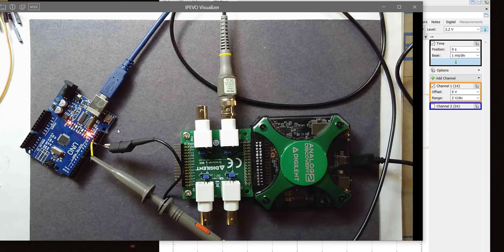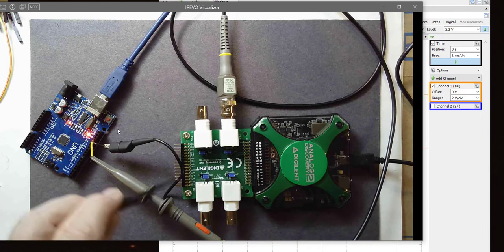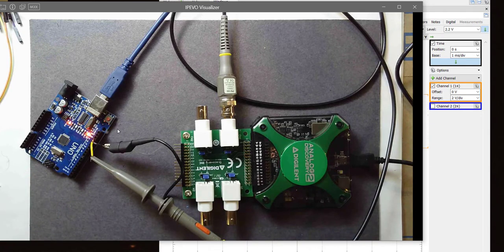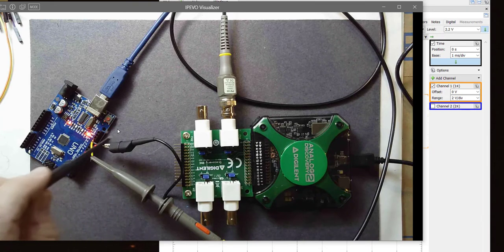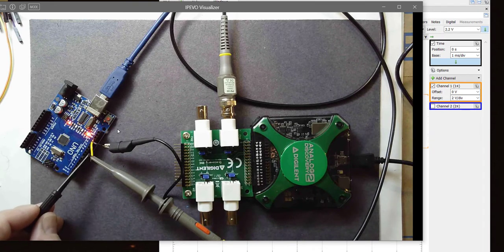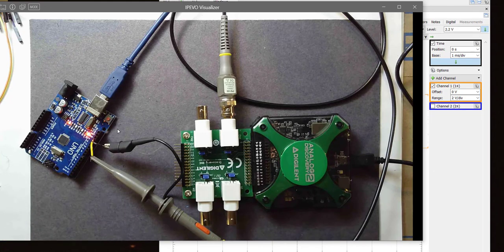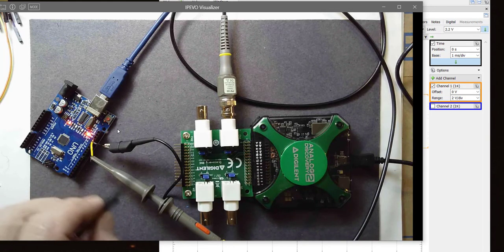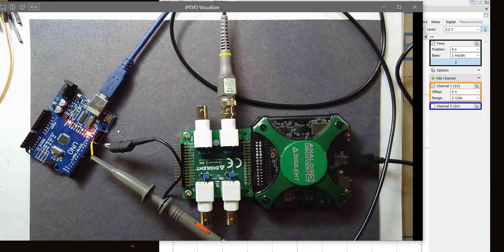For signals with a bandwidth of 35 megahertz or lower, roughly 10 nanosecond rise times or longer, this long loop, as we'll see in a minute, is really okay. It's not going to distort the signal very much. It's certainly an acceptable level. If we look at a rise time that is shorter than 10 nanoseconds, in other words, using another scope, then we're going to want to do what we can to reduce the loop inductance of that tip, and that's where using a special ground clip on the end is going to come in. And we're going to use that when we look at some of the circuit board connections as well, because it makes for a very convenient way of connecting into some of our circuit boards. But for now, using the ground lead and short wires is perfectly acceptable, and it's convenient.